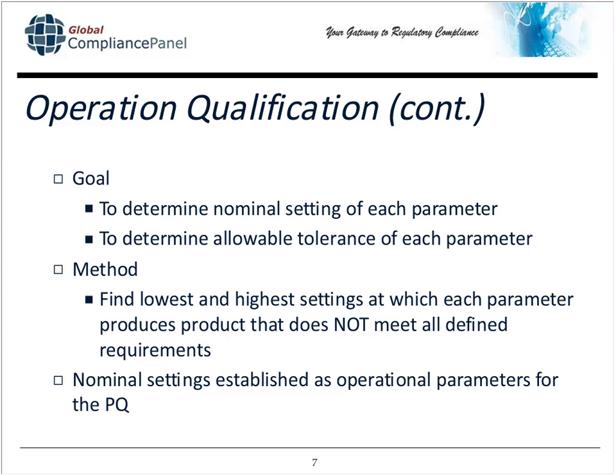So you want to develop your goal during the OQs to determine the nominal setting for each parameter, which is to say, this particular sealing machine on this particular pouch is to be set at what temperature, what pressure, what dwell time. Because what happens quite often is that your firm may not make enough product of that one particular product using that sealing machine. So you may use multiple pouches on the same sealing machine. So the process that you're going to validate is, let's call it small pouch, which has its own nominal settings that are different than big pouch.